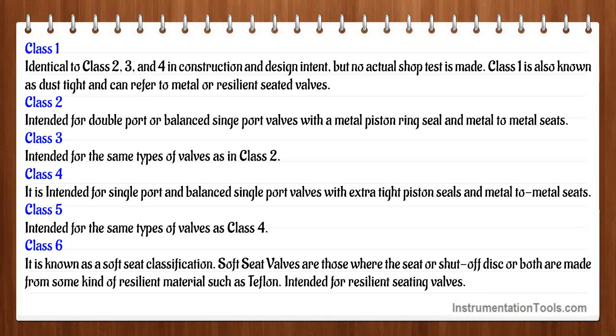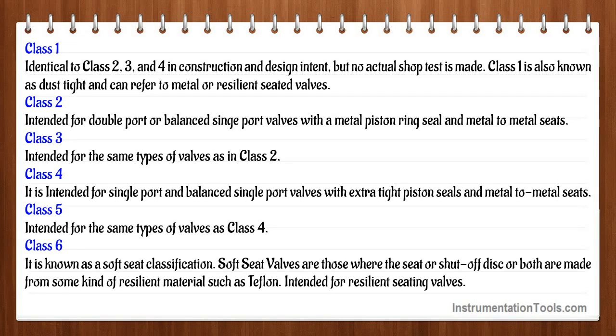Class 2 is intended for double port or balanced single port valves with a metal piston ring seal in metal-to-metal seats. Class 3 is intended for the same types of valves as Class 2. Class 4 is intended for single port and balanced single port valves with extra tight piston seals in metal-to-metal seats. Class 5 is intended for the same types of valves as Class 4. Class 6 is known as a soft seat classification — soft seat valves are those where the seat, shut-off disc, or both are made from resilient material such as Teflon, intended for resilient seating valves.